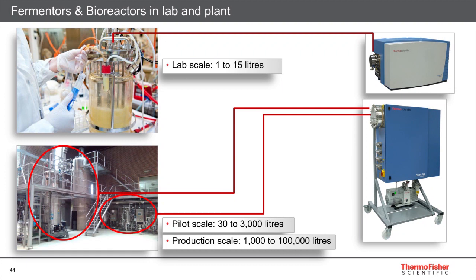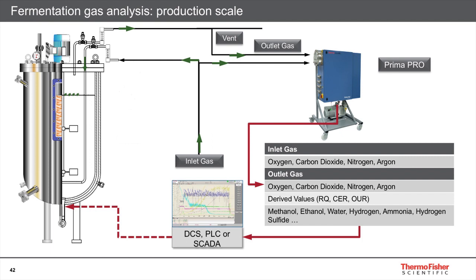There are a range of platforms suitable for lab environments — a benchtop version — or for more demanding industrial installation conditions with an industrially packaged mass spectrometer. Both share the same magnetic sector technology, just packaged differently. The primary function is monitoring fermentation and cell culture processes by measuring the composition of inlet or sparge gas and comparing that with the outlet gas from the headspace of a fermenter.